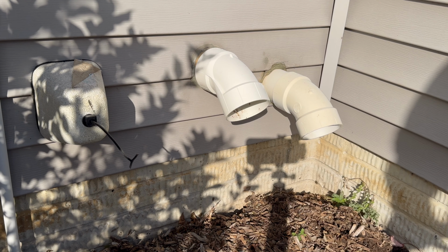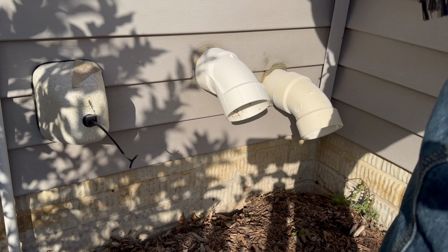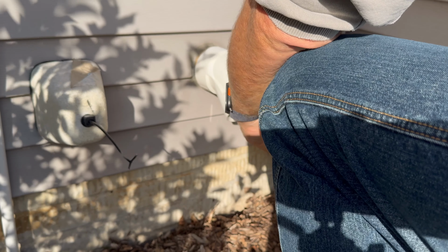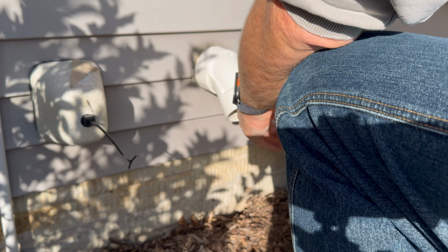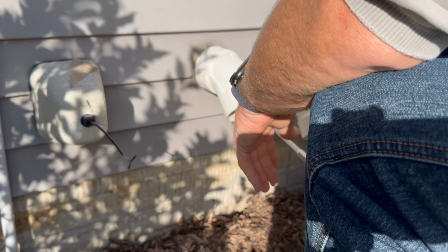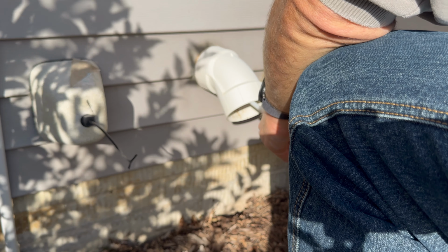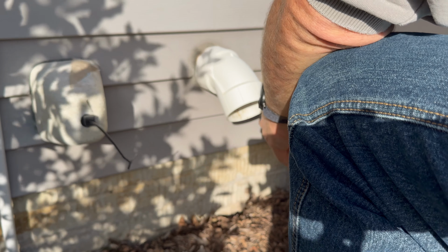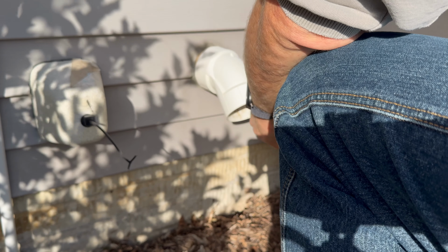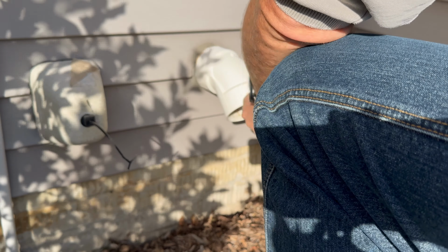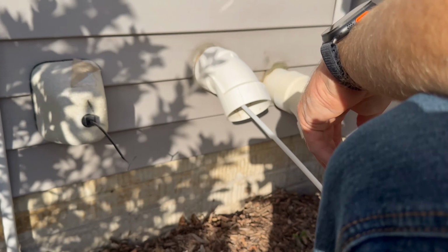Alright, I have the vent pipes disconnected on the furnace and water heater ends so I don't push debris into the units. I have to push from the outside in because there are some pretty radical turns where the pipes go from the basement to the outside, and while I'm impressed with how well this dryer vent kit pushed through the system, at about 20 feet away I couldn't get enough push on it to go past those bends.